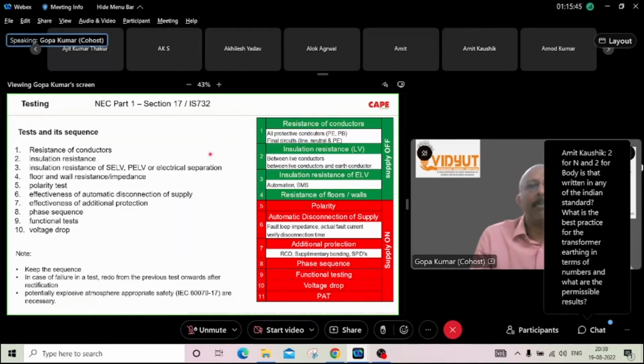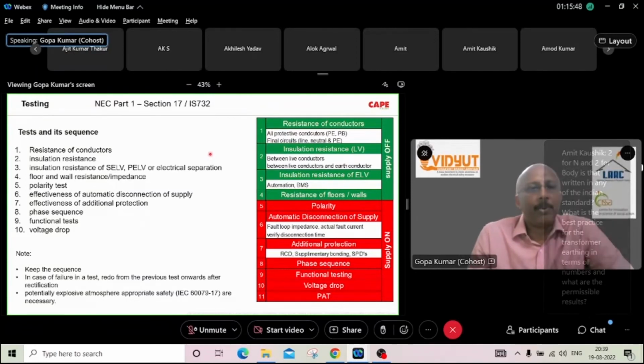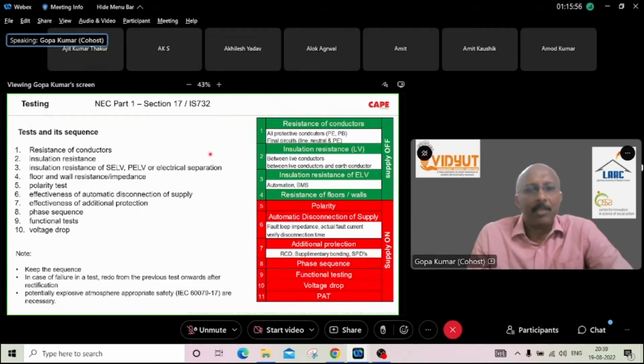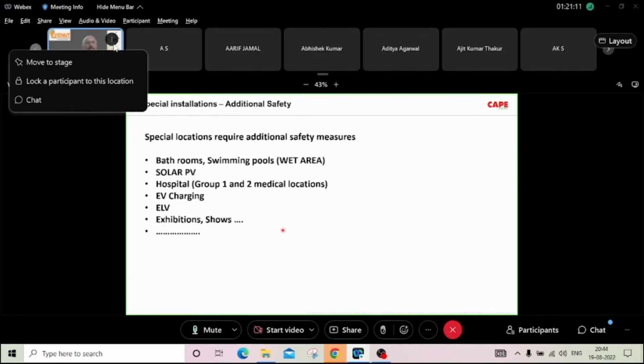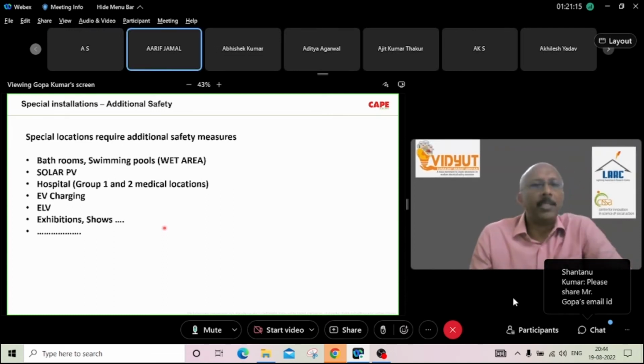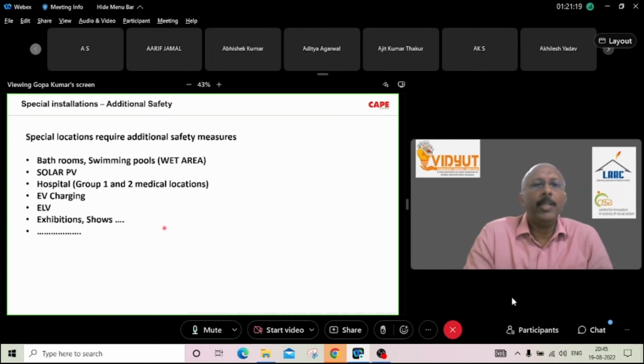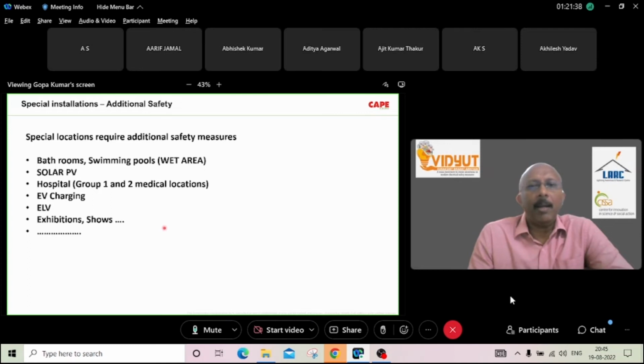But basically, the simple method which I wanted to explain is, if these tests are carried out properly and if the mistakes are rectified, the chance of an accident is almost nil. Some installations require additional safety measures. Say, for example, sometimes an instrumentation system in an industrial premise cannot afford to disconnect the supply in case of a fault. So fundamentally, the electrical supply system is classified into two. Earthed system, where the protective device should disconnect the supply before it creates fire or an accident. Unearthed system is possible in critical places where continuity of supply is necessary. That means for an instrumentation system, even under a fault condition, tripping of the power supply will be a problem. It can lead to other accidents.